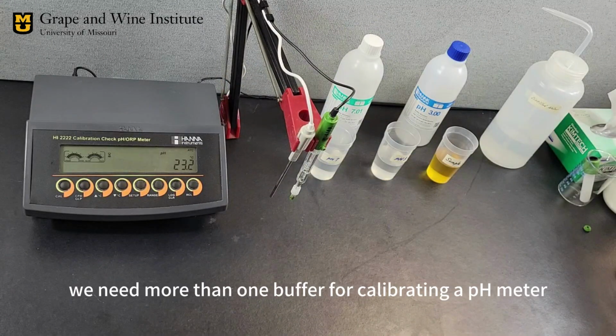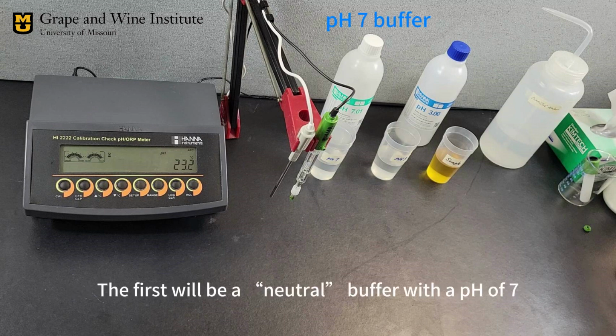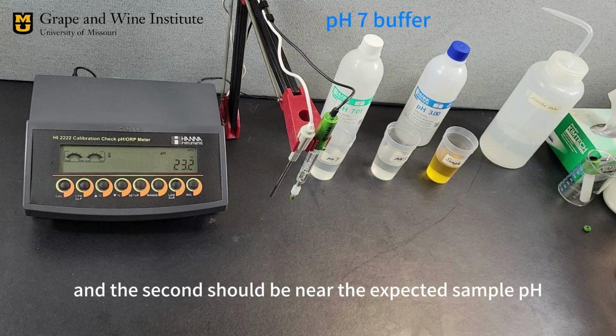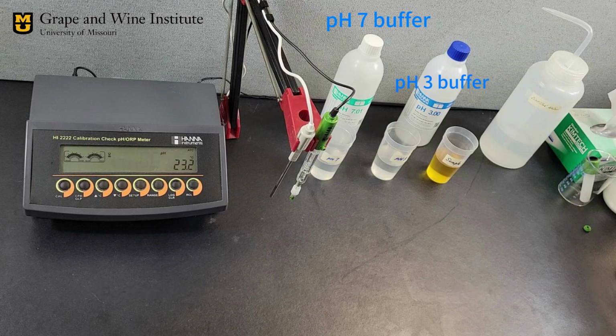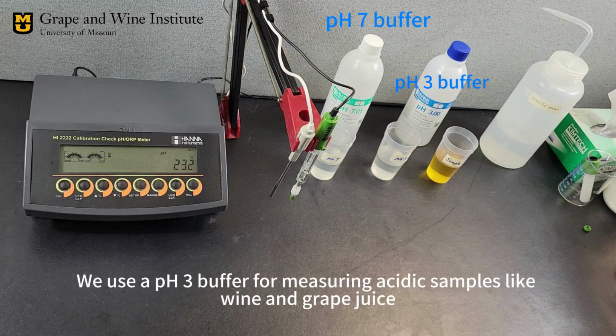Generally, we need more than one buffer for calibrating a pH meter. The first will be a neutral buffer with a pH of 7, and the second should be near the expected sample pH. We use a pH 3 buffer for measuring acidic samples like wine and grape juice.